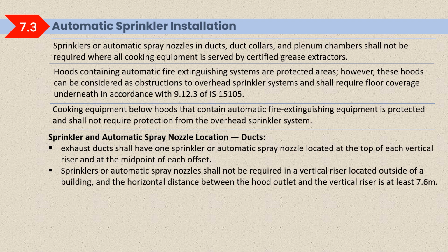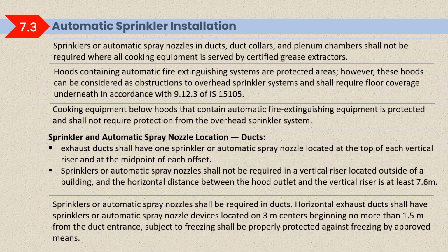Sprinkler and automatic spray nozzle location. Exhaust duct shall have one sprinkler automatic spray nozzle located at the top of each vertical riser and at the midpoint of each offset. Sprinkler or automatic spray nozzle shall not be required in a vertical riser located outside a building, and the horizontal distance between the hood outlet and the vertical riser is at least 7.6 meter. It is not required there. Sprinkler or automatic spray nozzle shall be required in ducts. Horizontal exhaust duct shall have a sprinkler or automatic spray nozzle devices located on 3-meter centers beginning no more than 1.5 meter from the duct entrance.